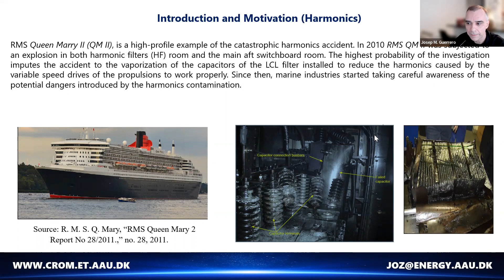If you look at the case of Queen Mary II, the main problem was caused by harmonics. The LCL filter that was installed to reduce harmonics ended up causing an explosion. That's why it's very important to account for harmonic instabilities, especially with the LCL filters connected to the converters and the capacitors shown here.